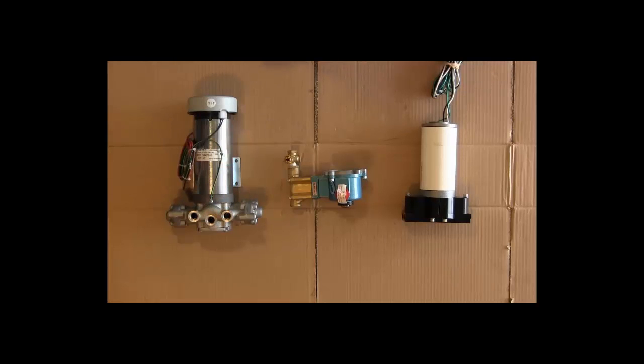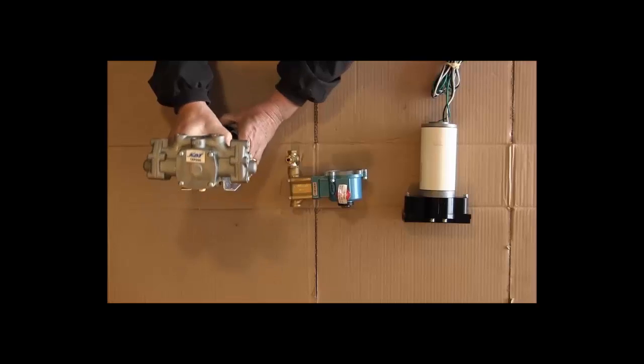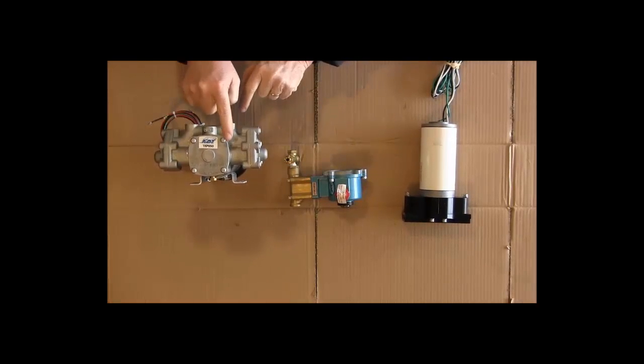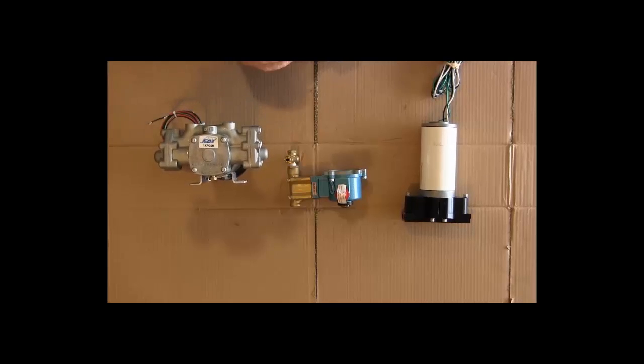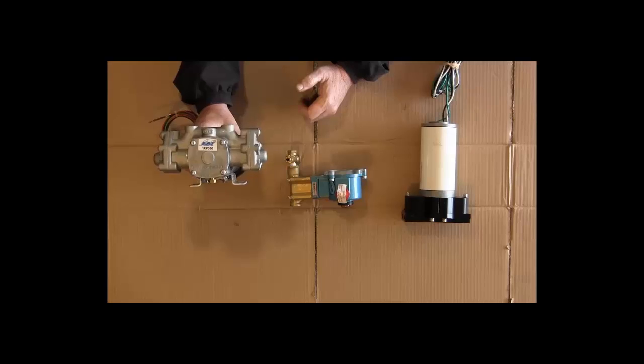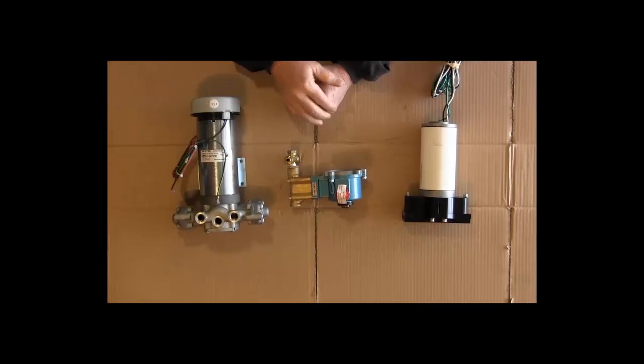When water goes in there, the crankshaft itself that causes the pistons to go back and forth is in this case right here, which is water lubricated. That means the bearing sleeves themselves are not steel on steel. They're more like a Teflon or a nylon coating on nylon, and then encased in water. That shows you kind of what that pump is like.